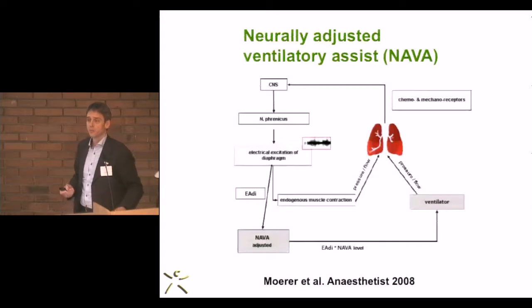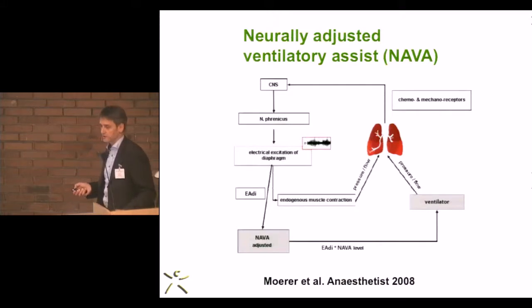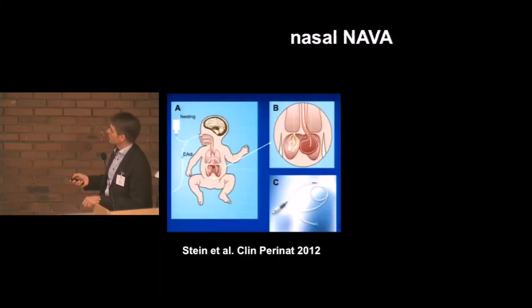And the other possibility to trigger non-invasively is this neurally adjusted ventilatory assist device, NAVA, that is available now on the market as well. What does that? This is a special feeding tube that has a built-in electrode. And this electrode is advanced down to the level of the diaphragm, sensing the electrical activity of the diaphragm as the onset of inspiration. And once this signal is detected, the ventilator would support the inspiratory effort of the baby.